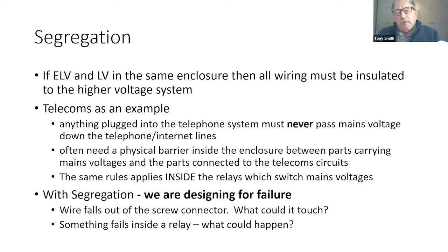So quite often you'll think about how do I cable tie the wires down, how do I restrain them so that even if they do come loose, they can't accidentally touch - the mains can't touch the ELV type wiring. So it becomes an issue about how you lay out the wiring inside a cabinet, how you restrain it, etc.